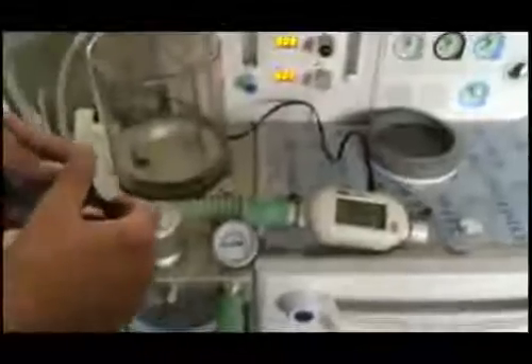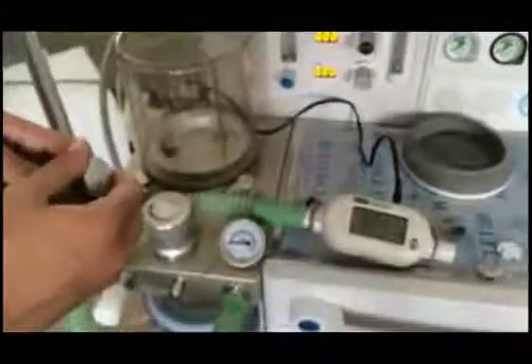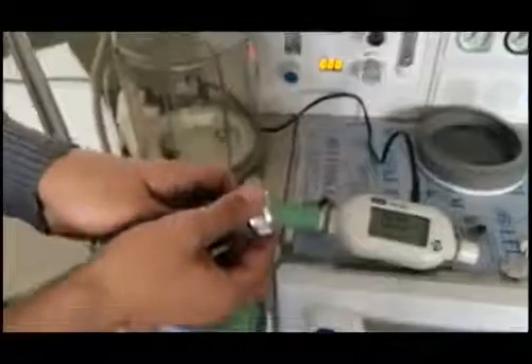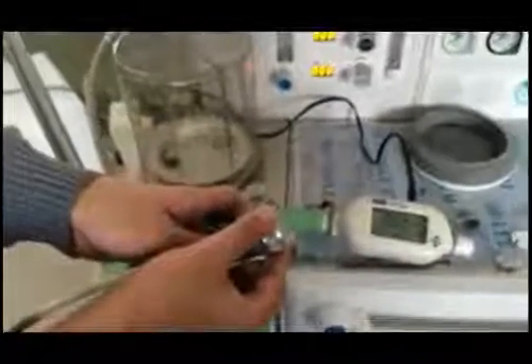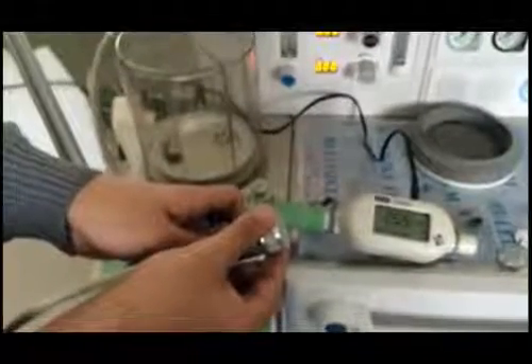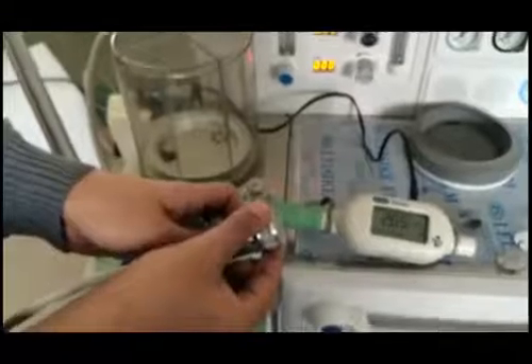Now we will perform the calibration for 3. Before pressing the key on the screen, please look at the flow meter. Right now the flow meter is displaying 0. We will rotate the throttle to increase the flow until we can see 3.